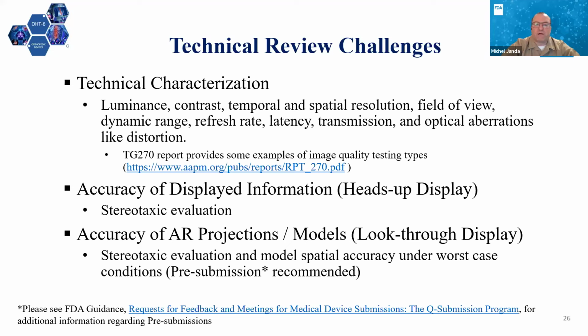These tests focus upon demonstrating the general performance of the projection technology and user experience. Beyond this technical characterization testing, OHT6 also asks that medical AR developers assess system accuracy using traditional stereotactic accuracy testing, as applicable. For systems intended only as a heads-up display, meaning the AR serves as a secondary information projection source only to the traditional primary 2D monitor, this testing is the same validation as requested for the stereotactic system itself.